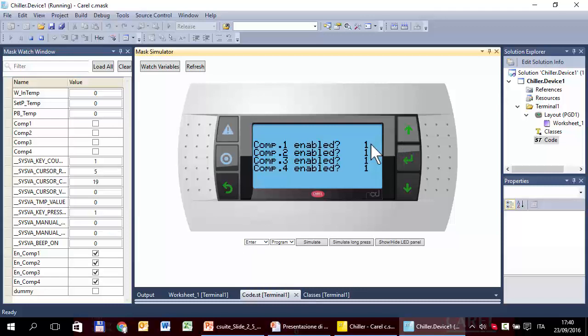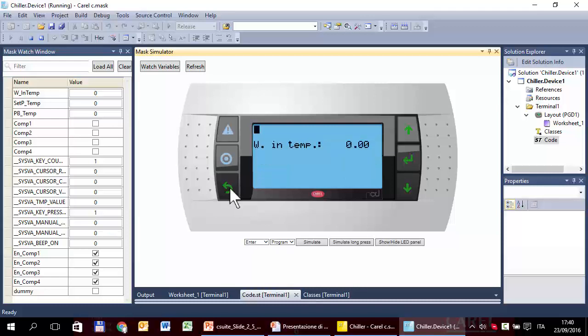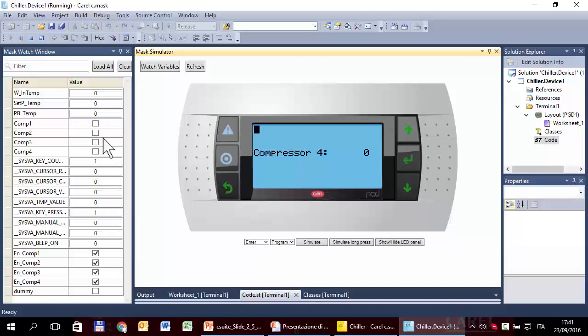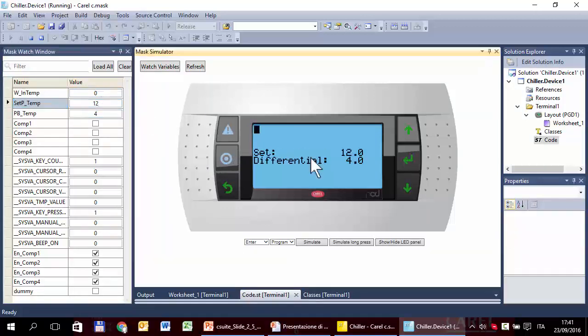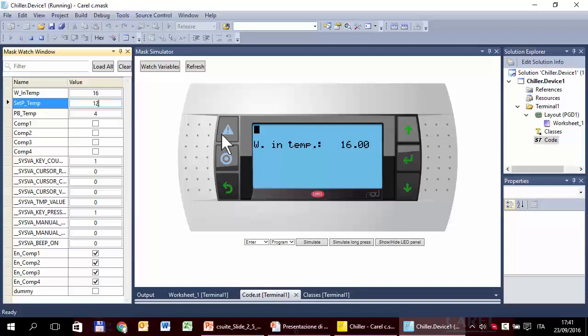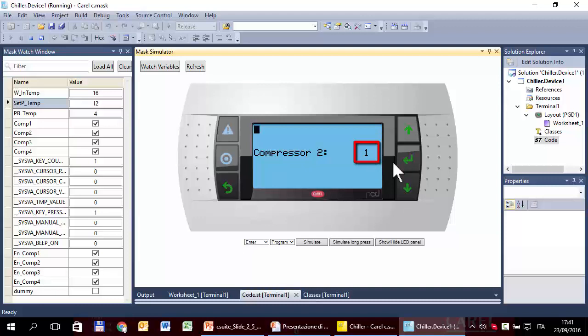This is the same condition as the previous exercise — all compressors enabled. So I expect to see all four masks: Compressor One, Two, Three, Four. I also expect the compressors to start if the temperature is high enough. The setpoint is zero, so I change it — twelve degrees setpoint, differential four degrees, temperature very high at 16. In fact, all four compressors are on: one, two, three, and four.